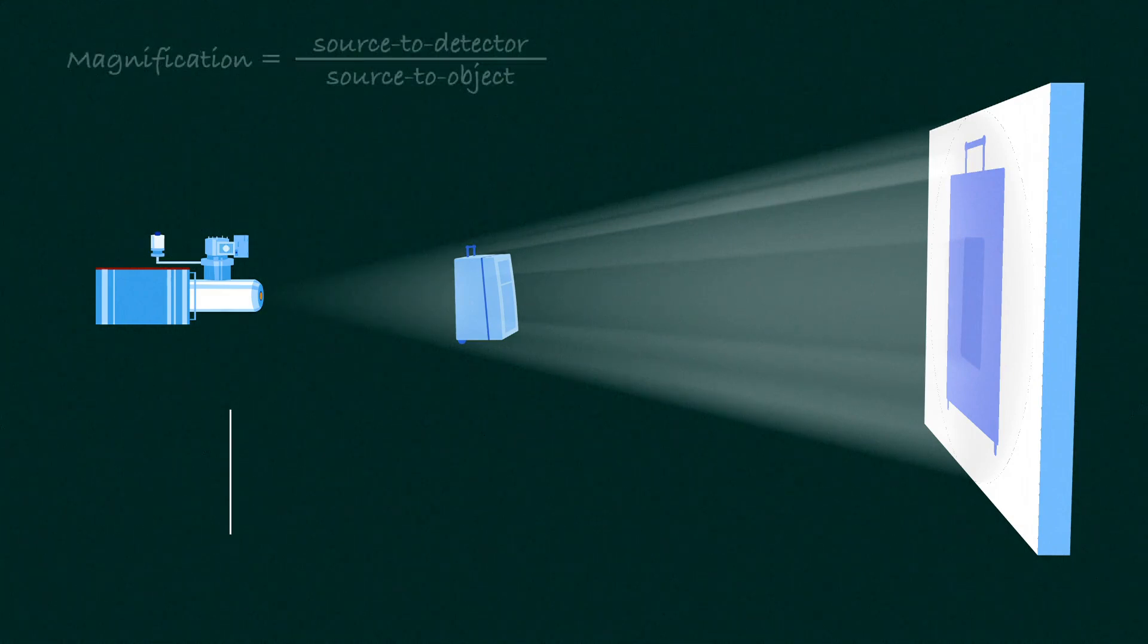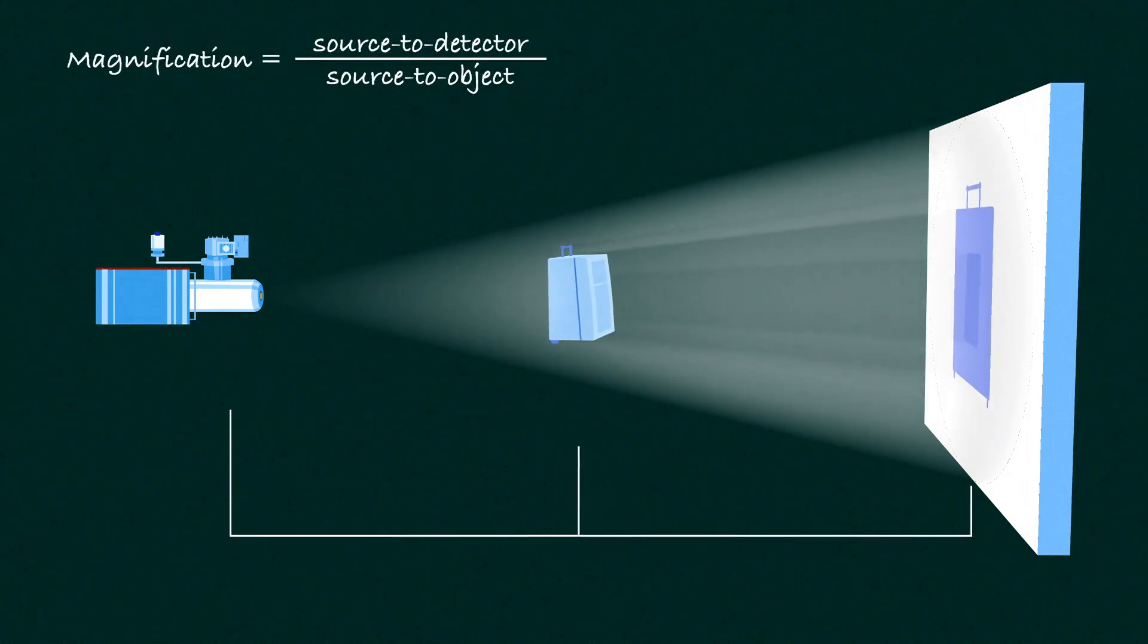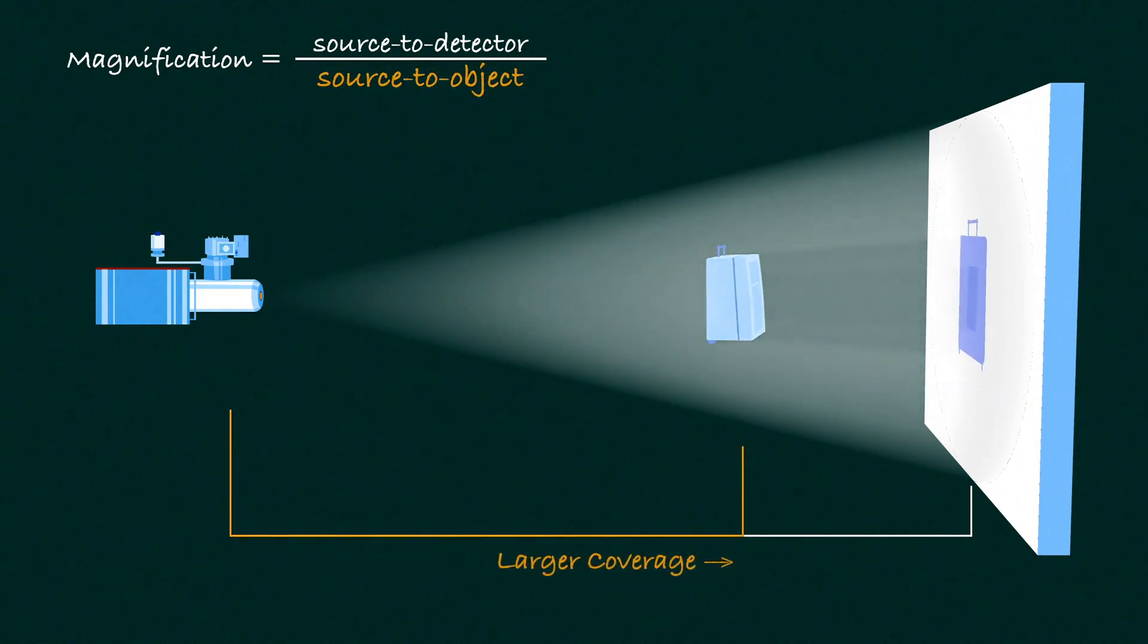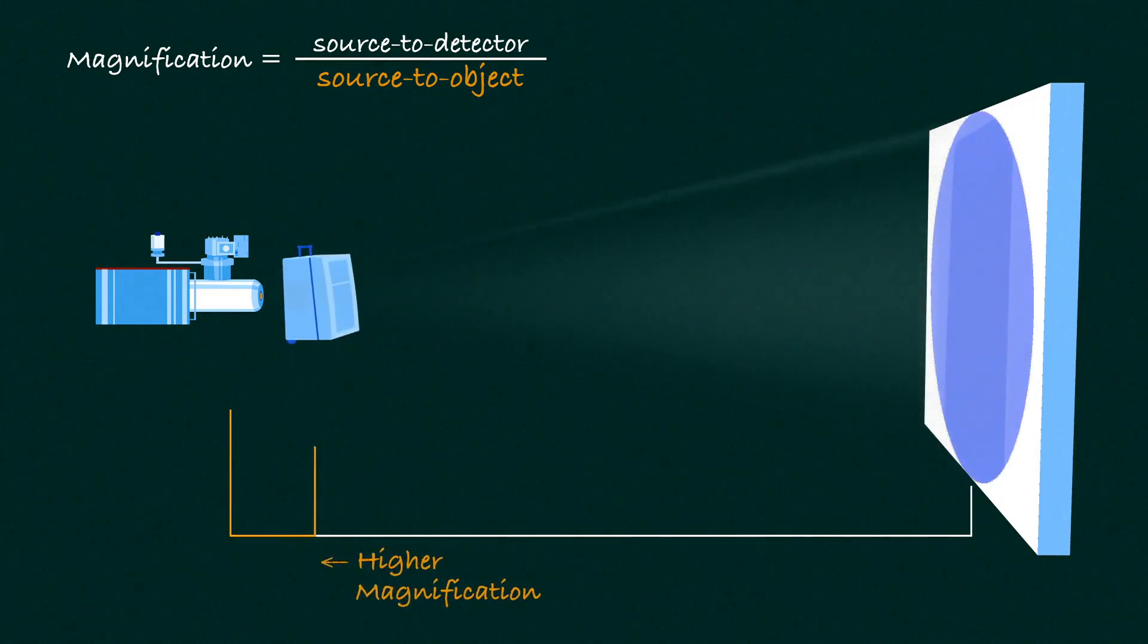With a point X-ray source, magnification and illuminated volume can be adjusted. Larger coverage is achieved by moving the object closer to the detector, while higher magnification is achieved by moving the object closer to the source.